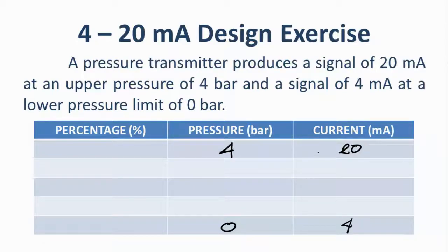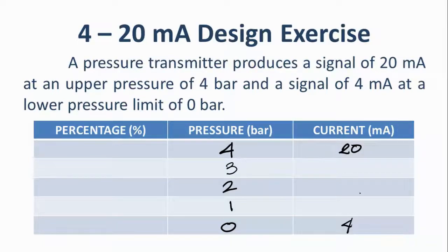We divide the range into 5 points. For pressure from 0 to 4 bar, the midpoint is 2, then 1 in between 0 and 2, and 3 in between 2 and 4 — giving us 0, 1, 2, 3, and 4 bar. For the current range of 4 to 20 mA, the midpoint is 12, then 8 between 4 and 12, and 16 between 12 and 20 — giving us 4, 8, 12, 16, and 20 mA.